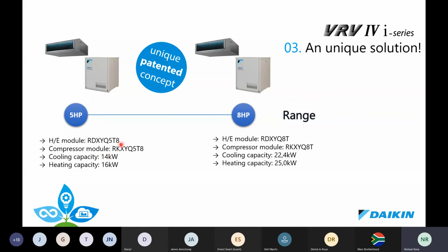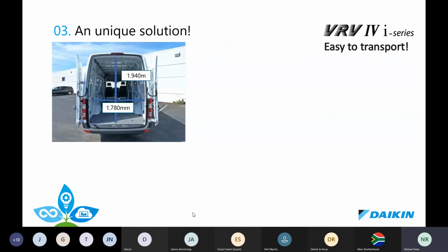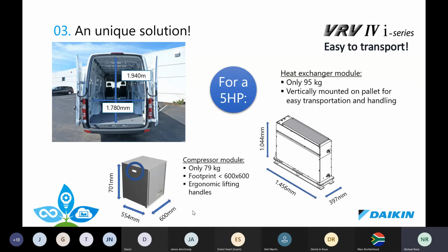So the capacities we have: previously we had only a 14 kilowatt cooling capacity. We've now got a 22 kilowatt, which is equivalent to our 8 HP system. Hopefully in the future, we'll go up to a 10 and then a 12. What's good about this is it's easy to transport. They can fit in the back of a transport buggy. That's the size of the fan module, which is the size of an indoor unit, right? In corrosive areas, I will advise that the indoor coil be corrosion treated, as you would normally do for full fresh air systems. The compressor module does not need a drain, and it makes less noise than a fridge.